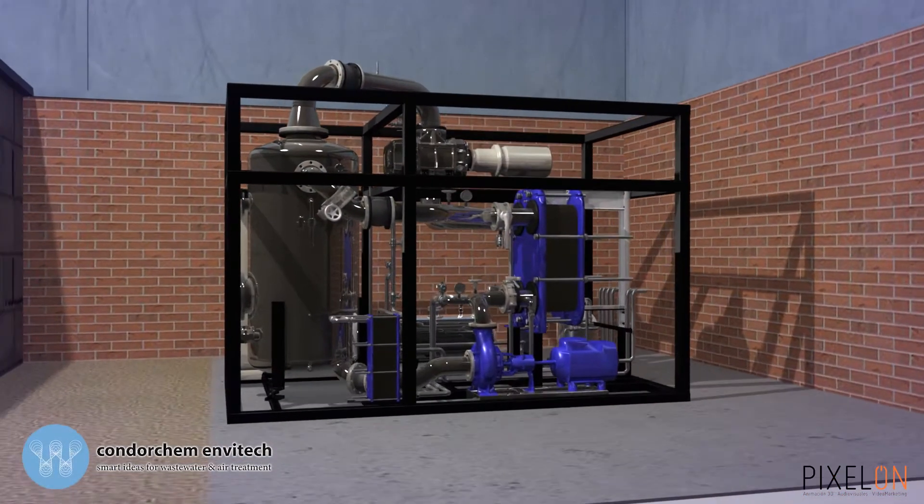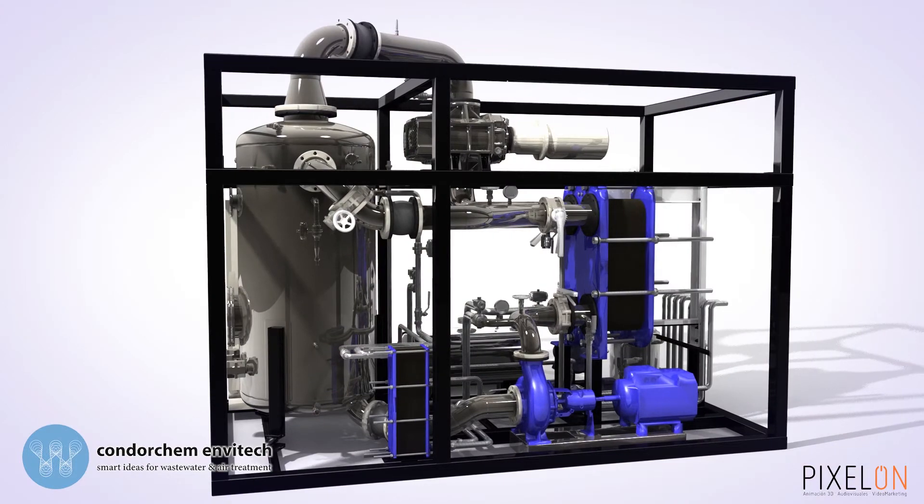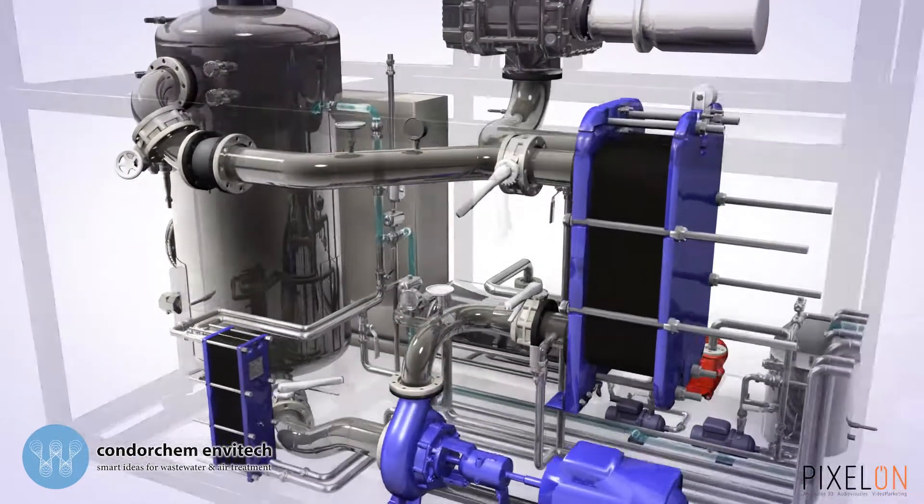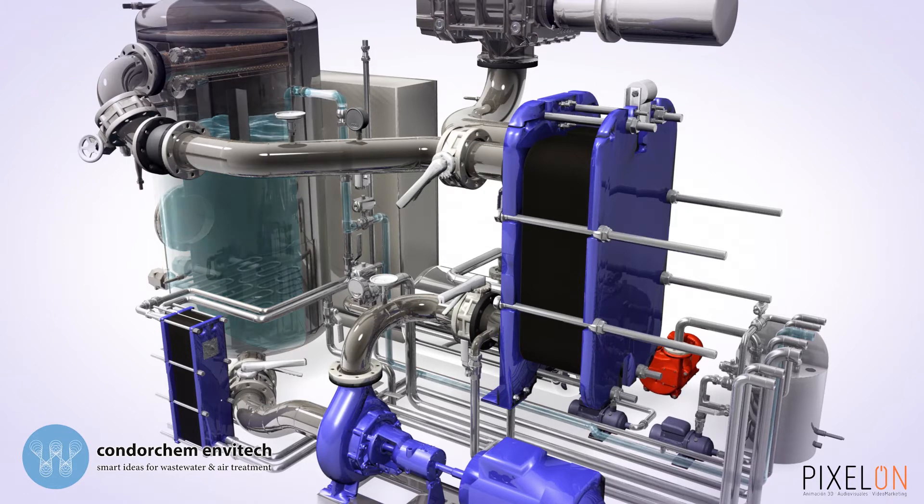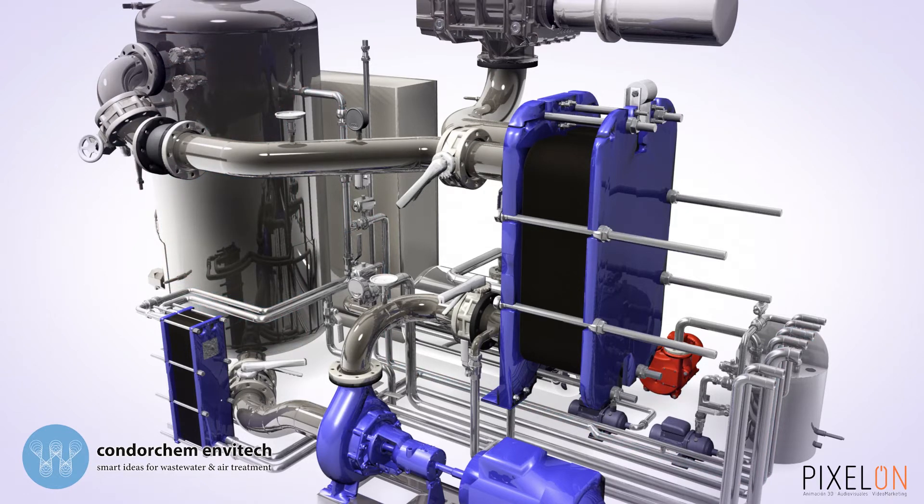When you turn the equipment on, the vacuum pump starts and the evaporator boiler fills up thanks to the vacuum, with values close to 600 mbar generated.